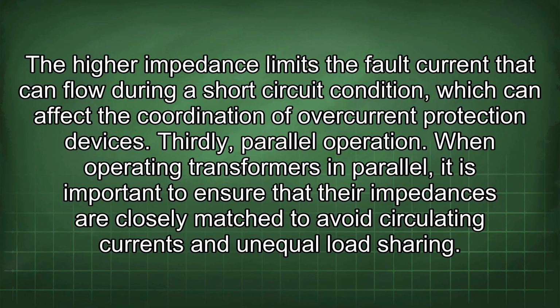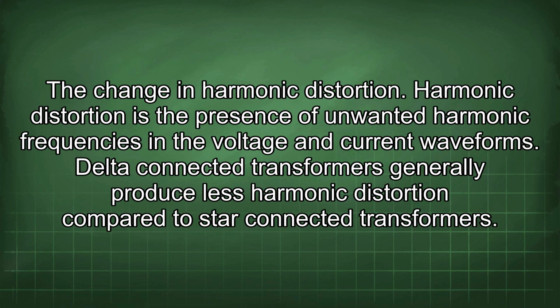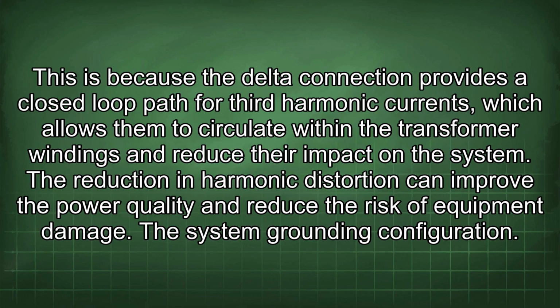The change in harmonic distortion. Harmonic distortion is the presence of unwanted harmonic frequencies in the voltage and current waveforms. Delta-connected transformers generally produce less harmonic distortion compared to star-connected transformers. This is because the delta connection provides a closed-loop path for third harmonic currents, which allows them to circulate within the transformer windings and reduce their impact on the system. The reduction in harmonic distortion can improve the power quality and reduce the risk of equipment damage.